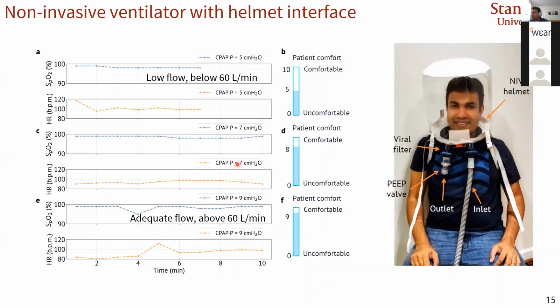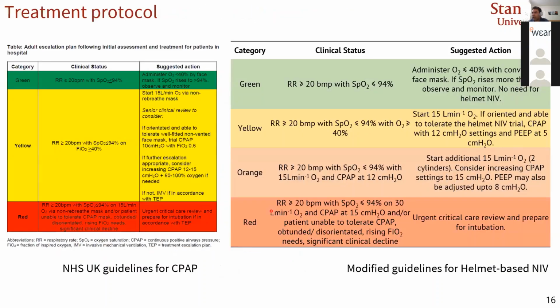And then finally, we tested on a person, and here I'm showing the different flow rates. So here I set the pressure at 5 centimeter water, and this is at a low flow, below 60 liters per minute. And here you will see some sort of fogging of the helmet. But if you increase the flow over 60 liters per minute, it becomes much more comfortable for the patient, and it is usable.